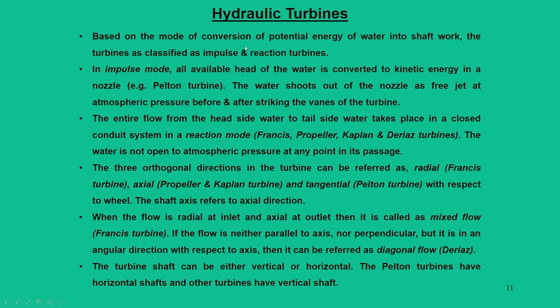Based on the mode of conversion of potential energy of water into shaft work, the turbines are classified as impulse and reaction turbines. In impulse mode, the available head of water is converted to kinetic energy in a nozzle, and then the water shoots out from the nozzle as a free jet at atmospheric pressure before and after striking the vane of the turbine.